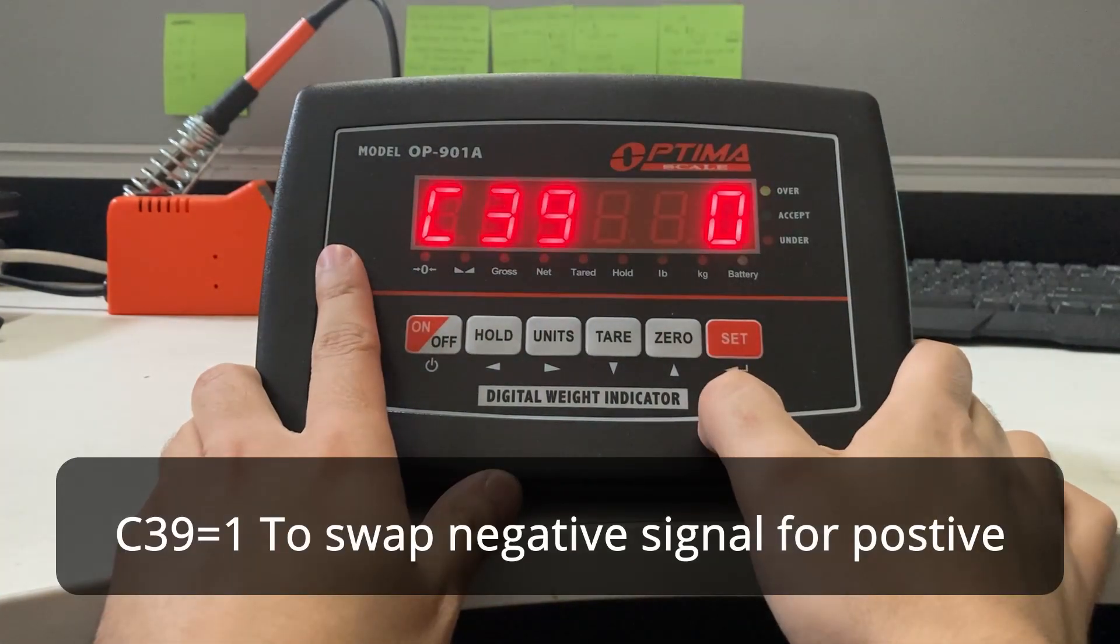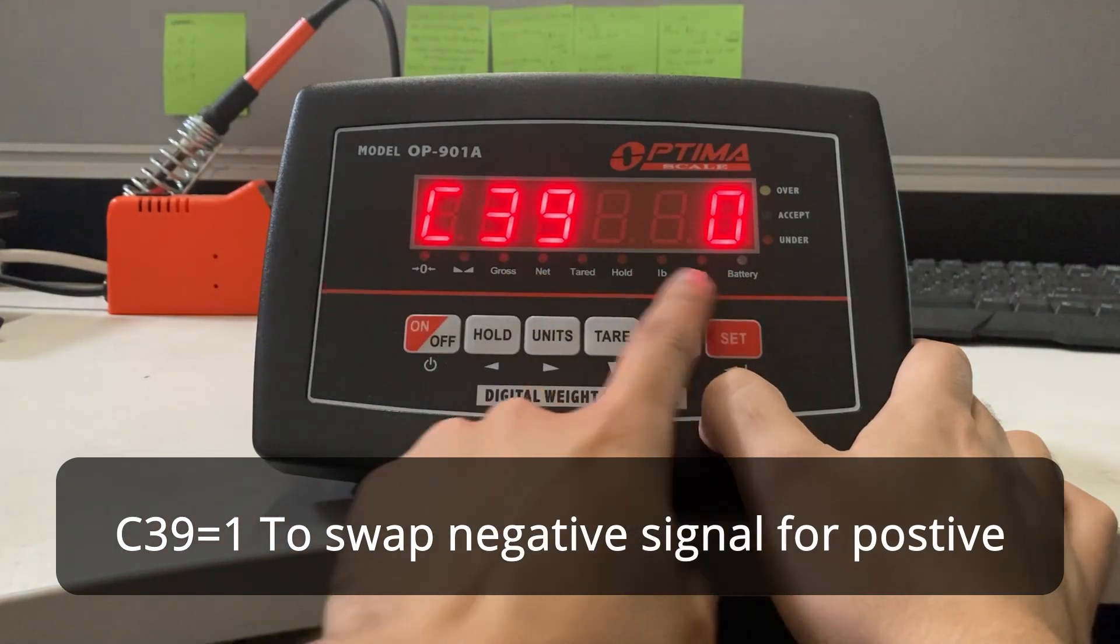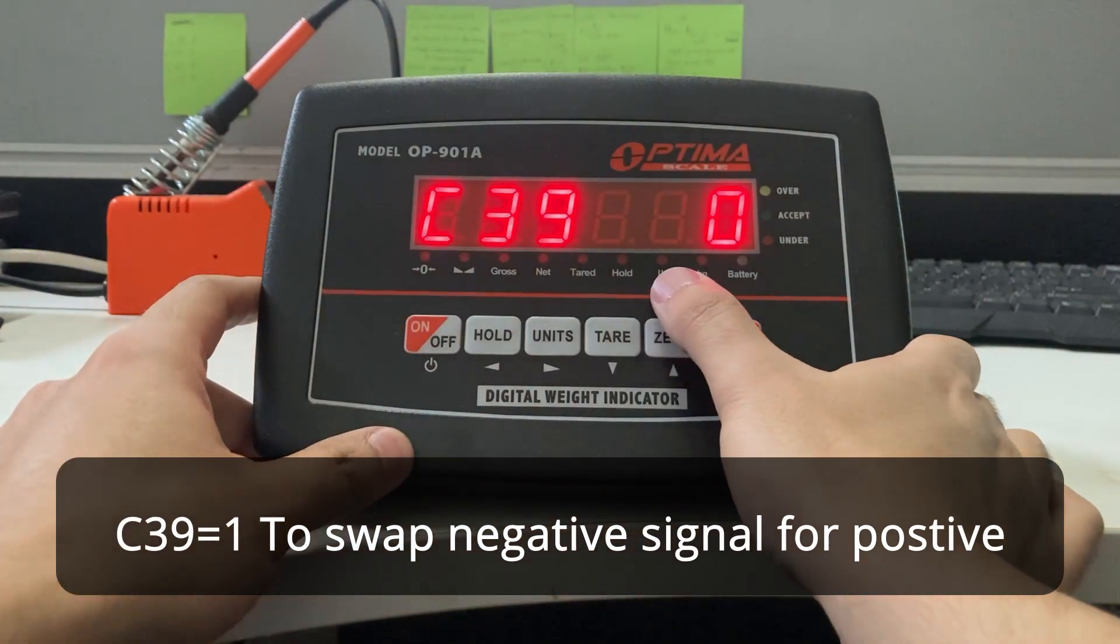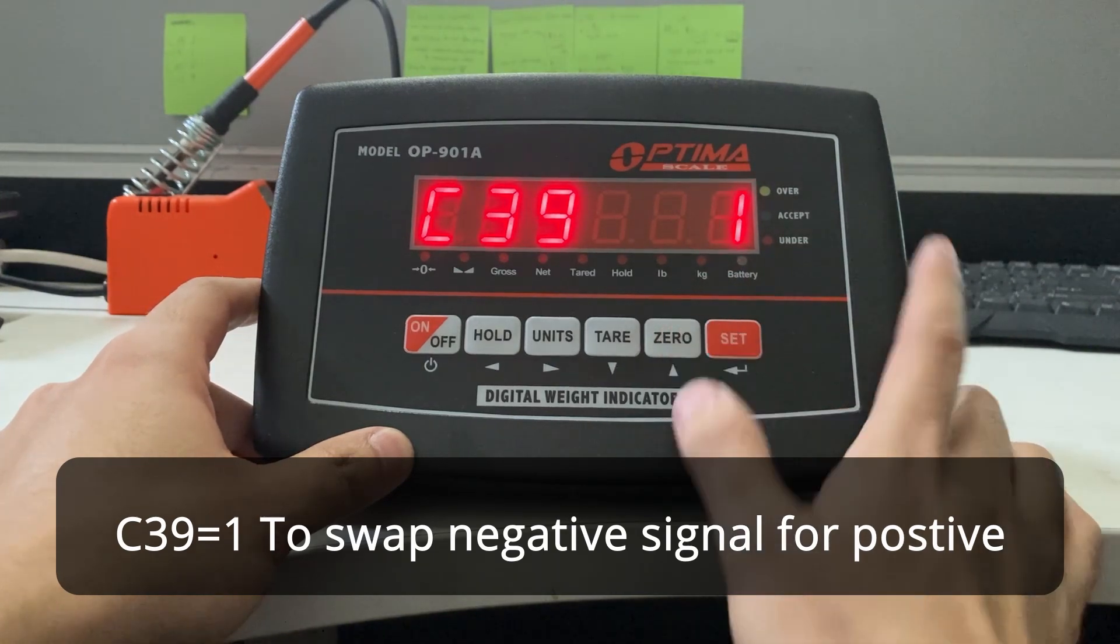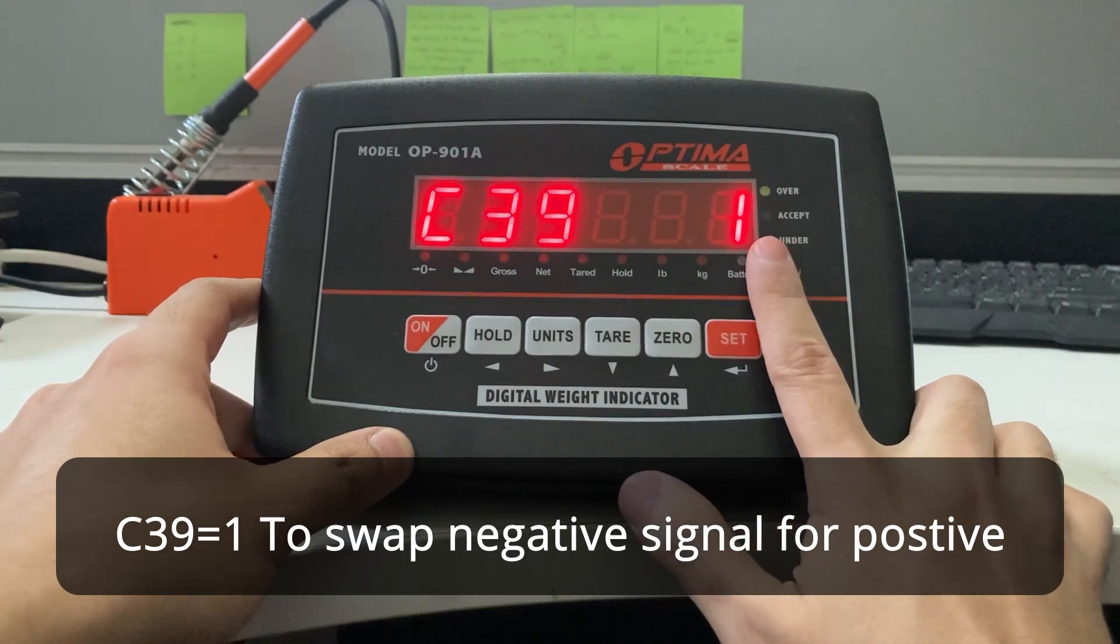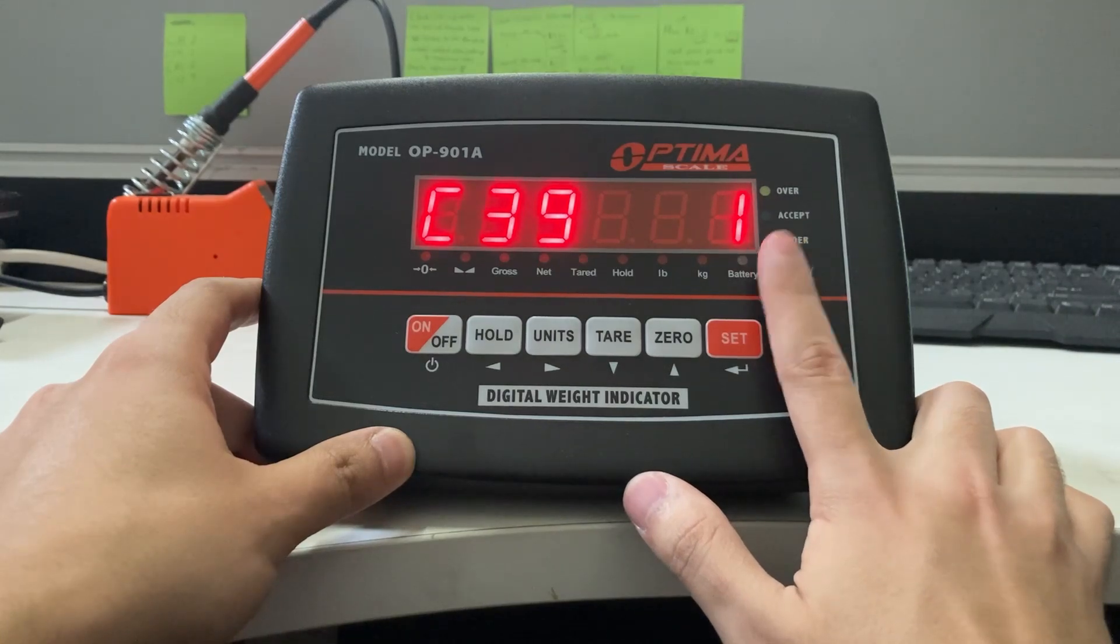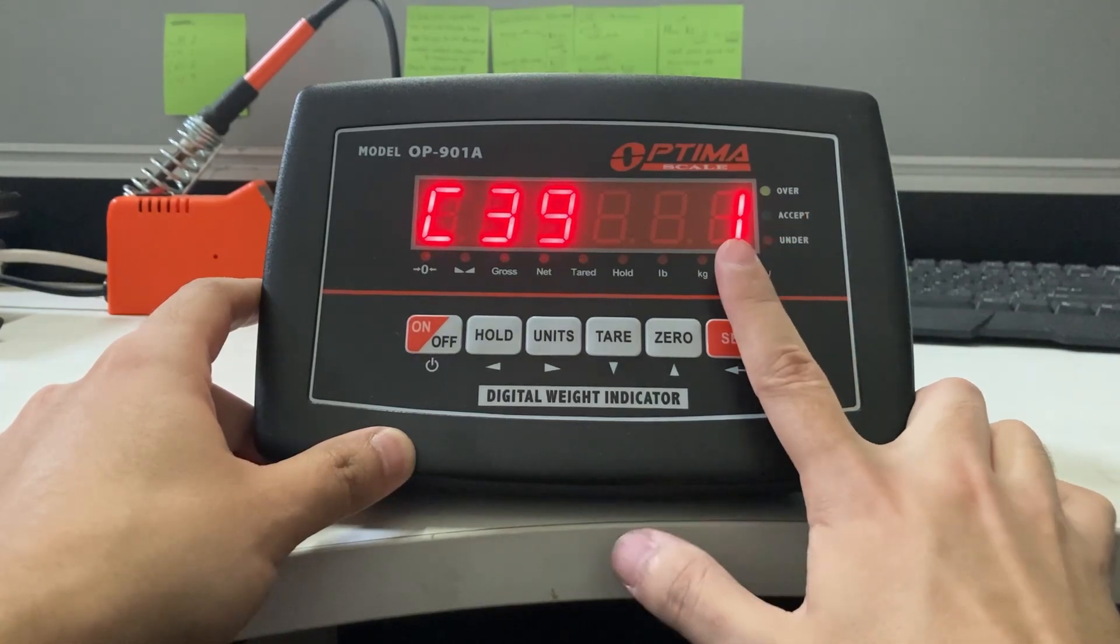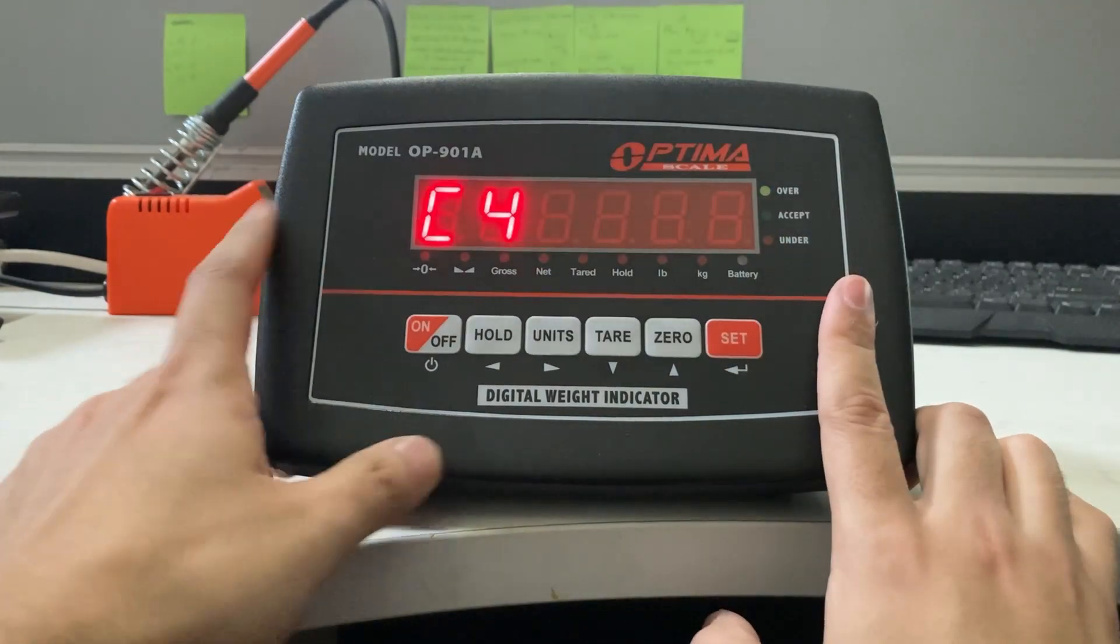Press that. Now you see C39 zero. Press the zero button to make it one. This will switch the signal on your indicator, so now a negative weight shows positive. C39 one. Press that.